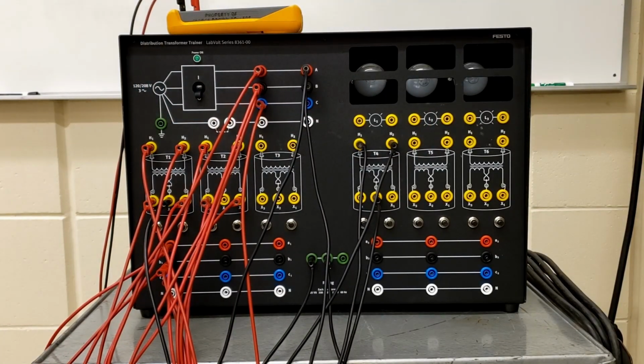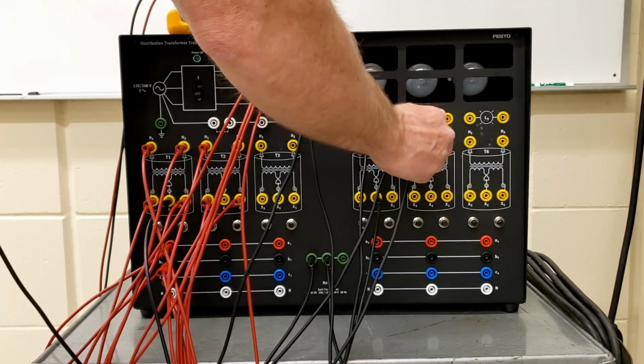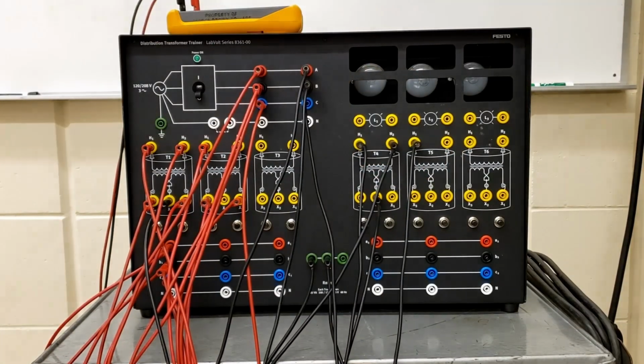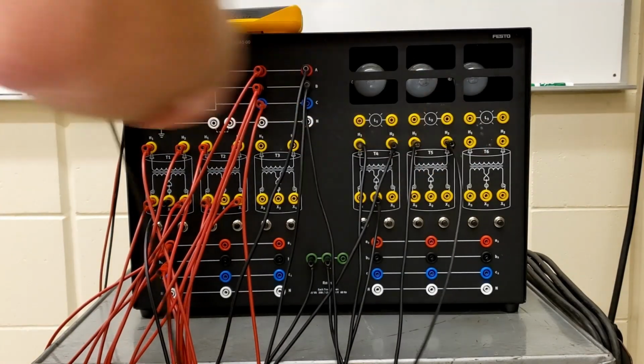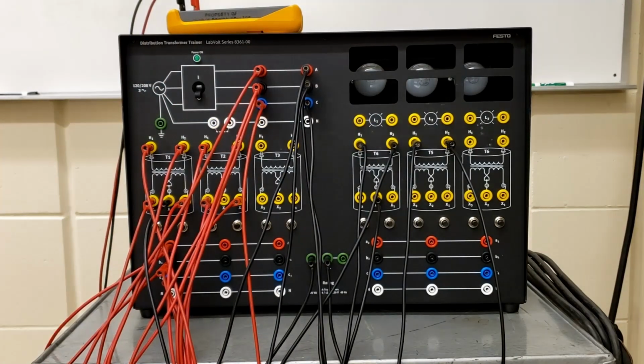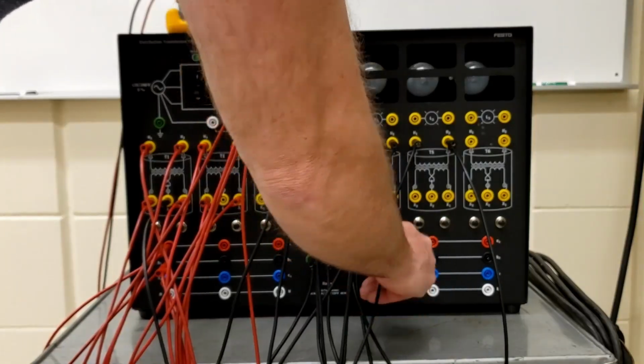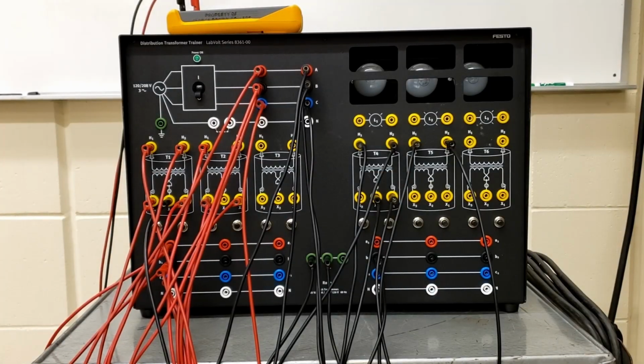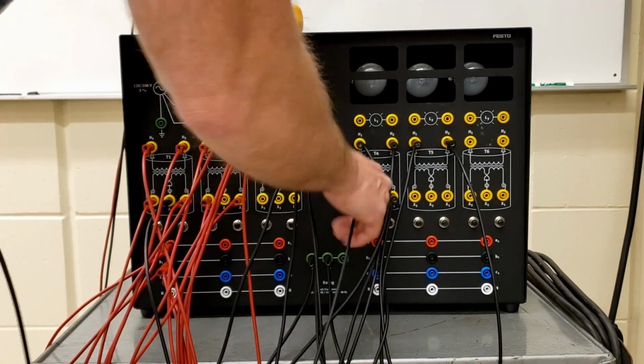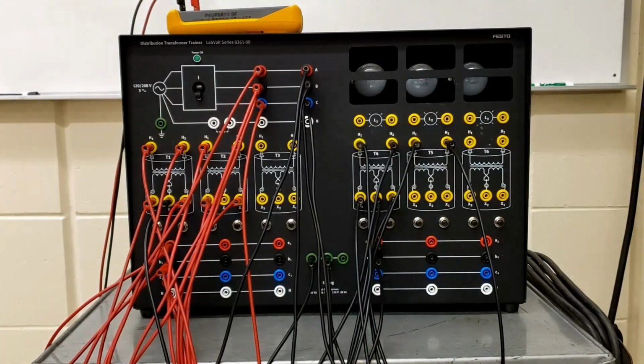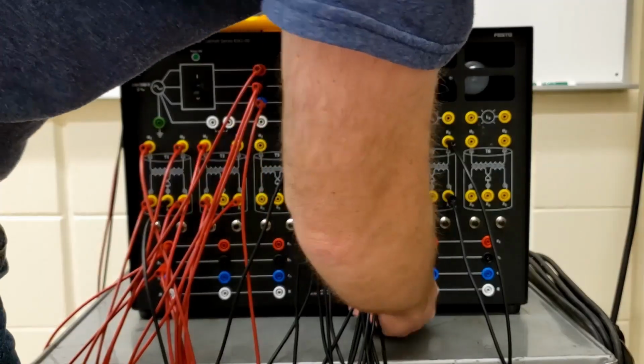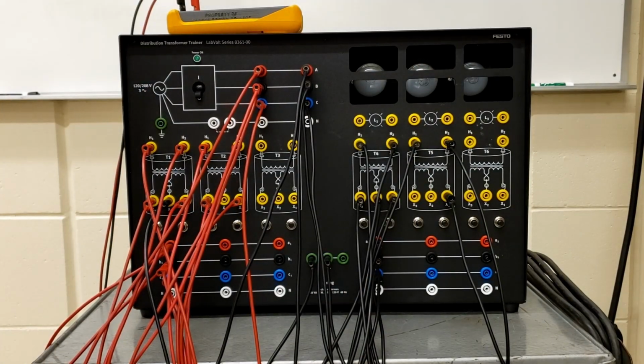Okay. H1 is feeding from B, so A to B, B to C. So this guy is going to be fed from B phase. And then, let's see, H2 is fed from C, yes? Yes. Okay, H2 is fed from C. Okay, now on the secondary side, we're going to do the 180. So X1 is going to tie into B. So X1 is going to feed the B phase. Okay, and X3 is going to feed A. Okay. And then on the second one, we got X1 feeding C. Looks good. And X3 is going to feed B.